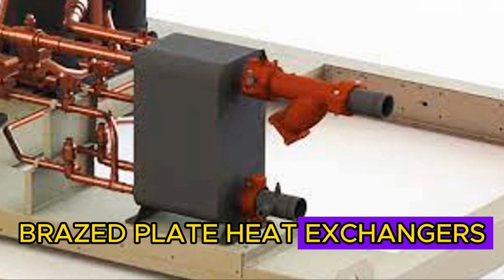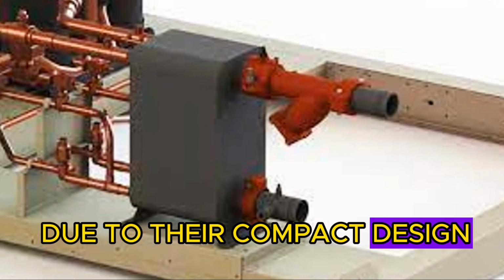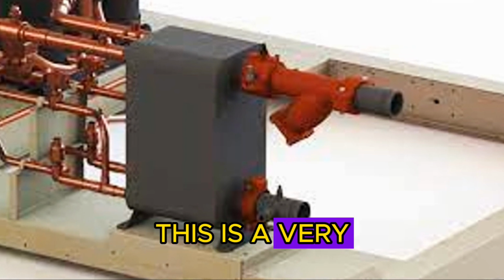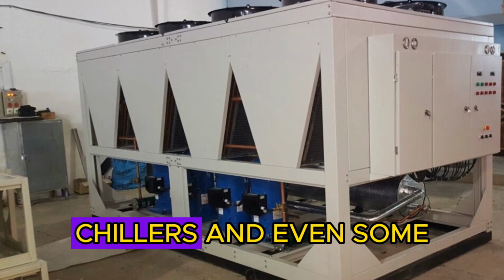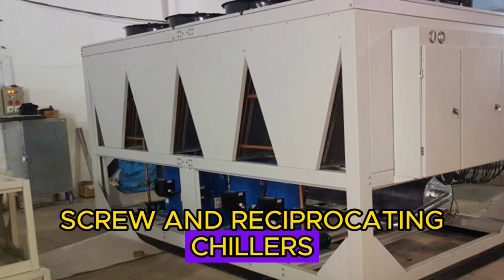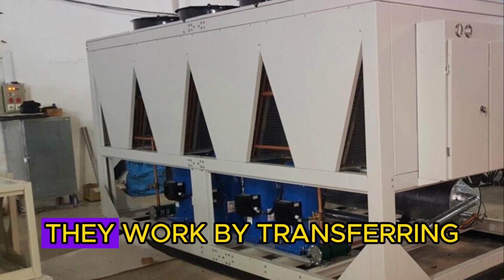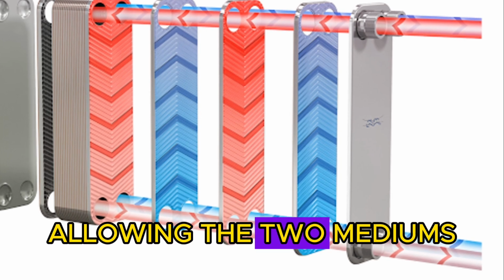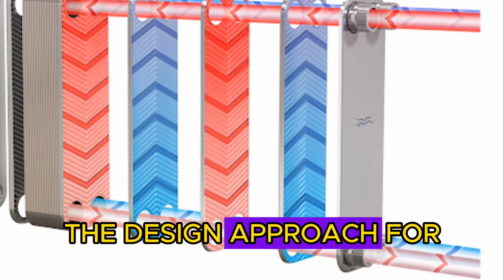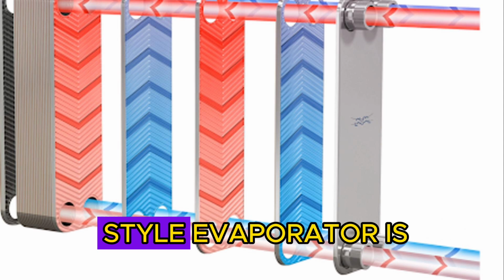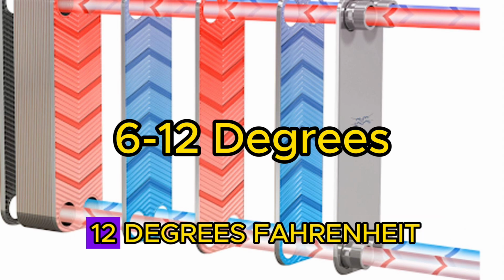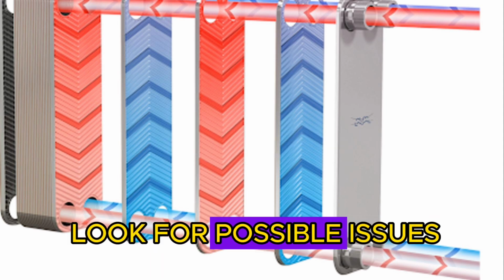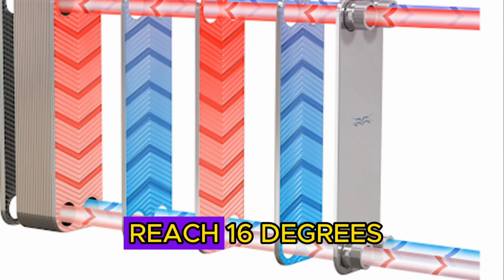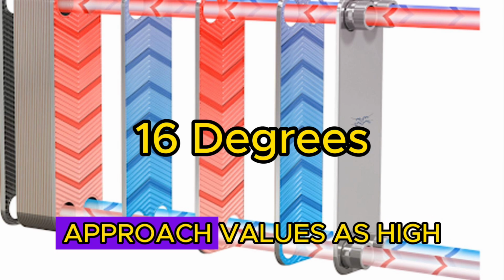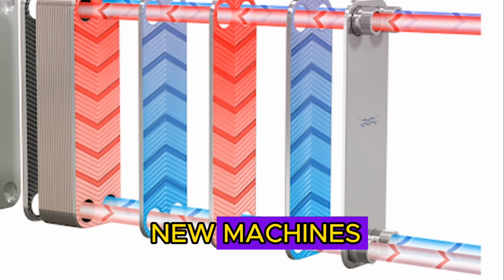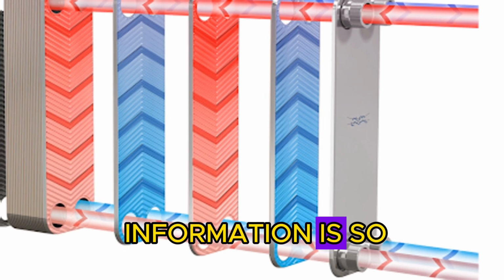Brazed plate heat exchangers are a popular choice due to their compact design and high efficiency. This is a very common style evaporator on scroll chillers, and even some screw and reciprocating chillers. Like every other heat exchanger, they work by transferring heat without allowing the 2 mediums to contact each other. The design approach for a brazed plate heat exchanger style evaporator is typically between 6 and 12 degrees Fahrenheit. I would begin to look for possible issues if the approach values reach 16 degrees. We have seen approach values as high as 18 degrees on new machines. That's why the manufacturer's information is so important.